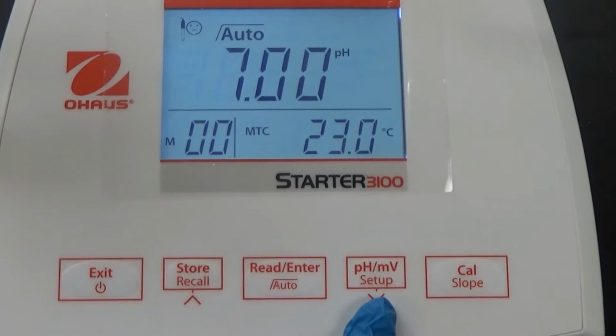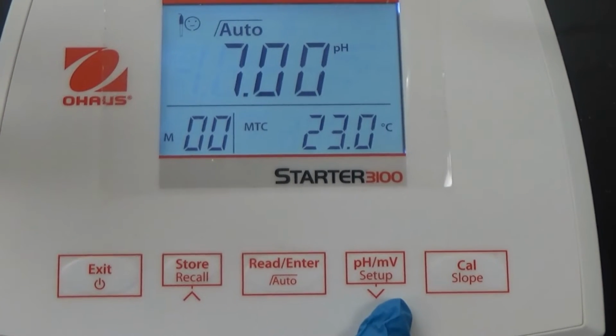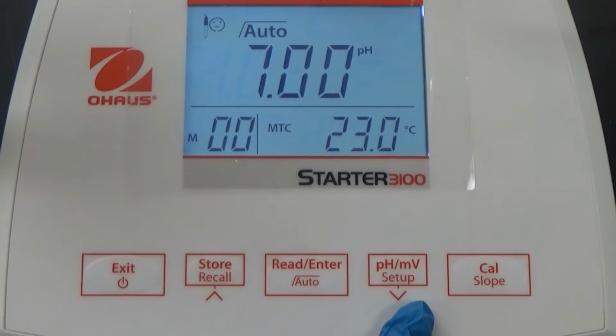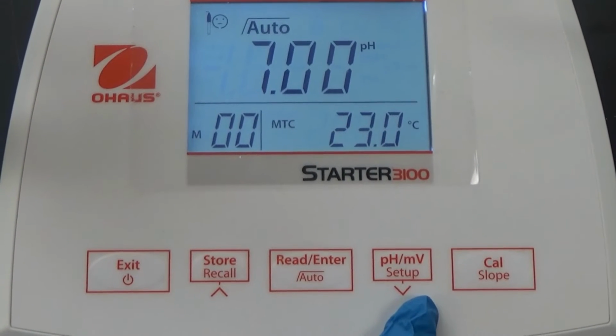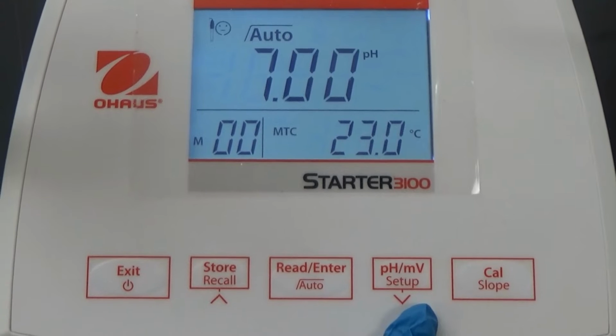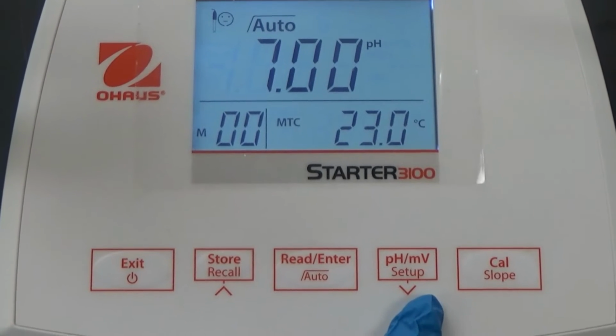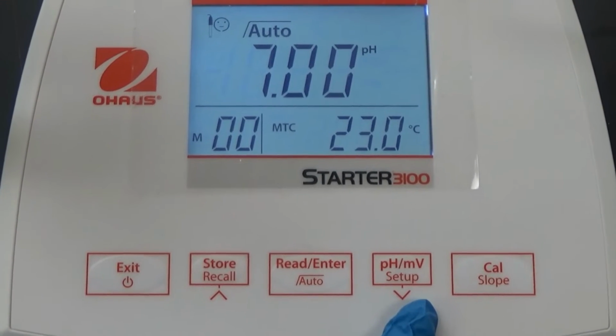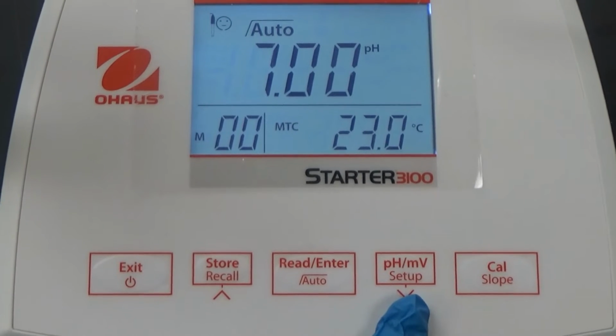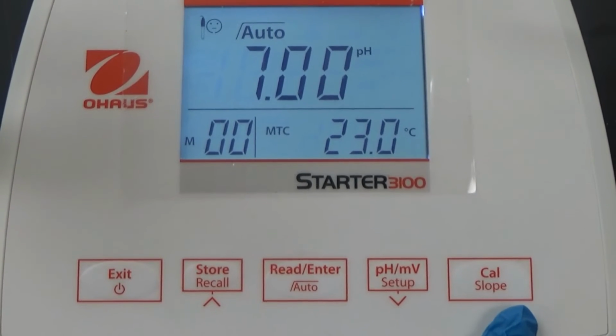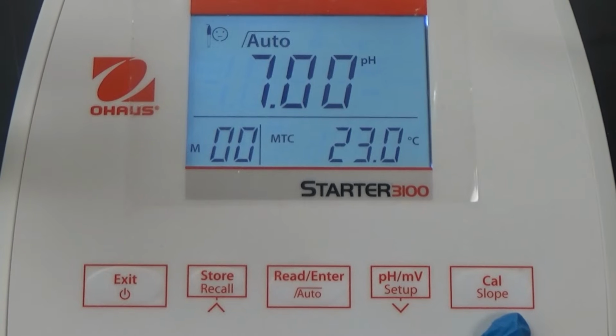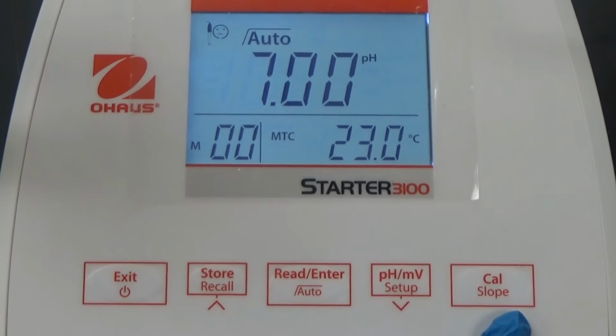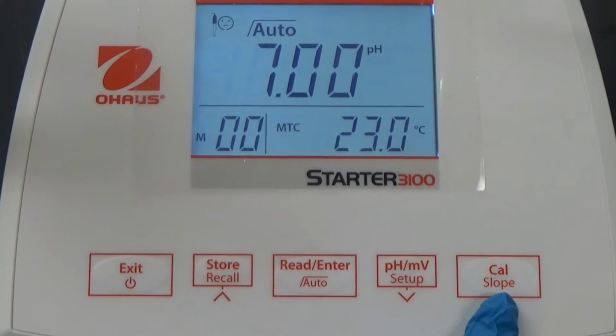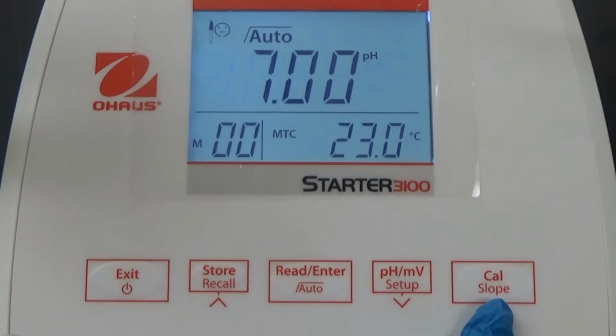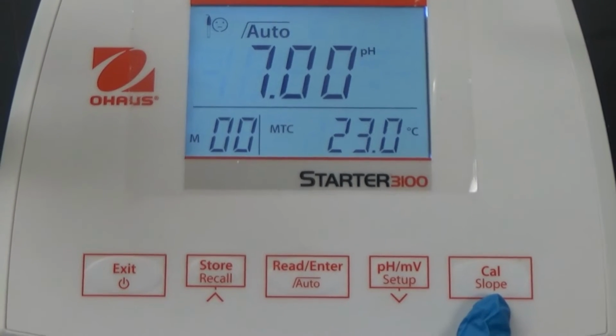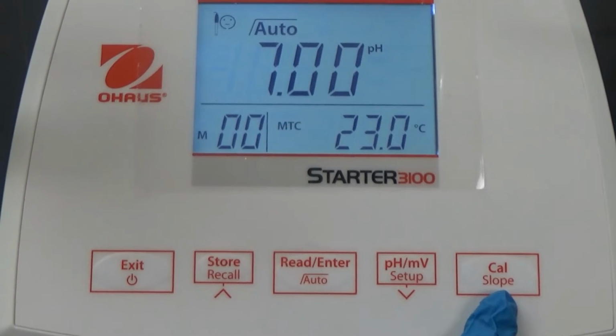The pH/millivolts and setup is not another button that you will really be using, but this is to set up another type of setting on the pH meter, and you won't need to use it when doing basic things. The cal is the button that you will press to begin the calibration, and the slope is to read back the slope of the data gathered from the calibration if you wish to see it.